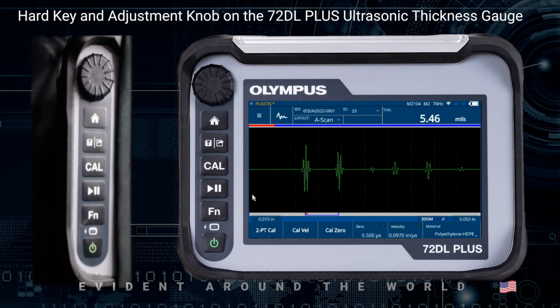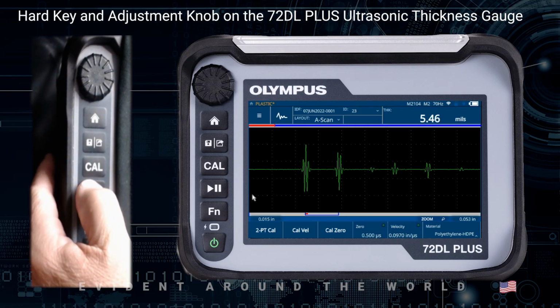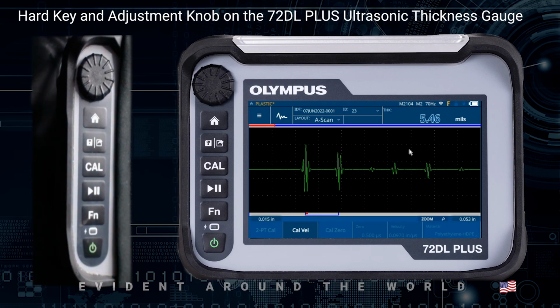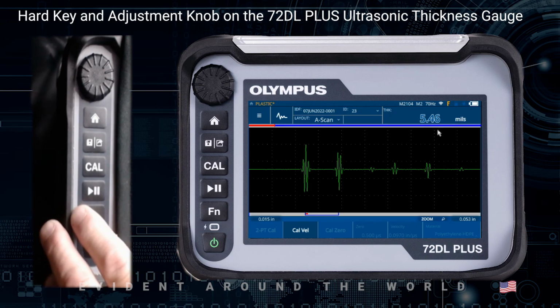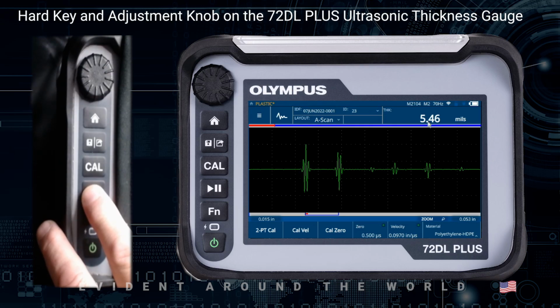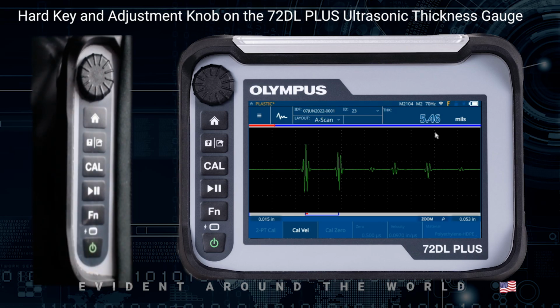Below the cal key is the pause and play key, or the freeze and unfreeze key, if you will. What this does is it simply pauses or freezes the display. So pressing it the first time will pause or freeze the display. You'll notice that a small F is displayed at the top of the display, and the thickness reading is displayed as an outline trace when it's frozen. When it's unfrozen, it goes back to a white solid number display, and as it's frozen, it goes into a reverse videoed outline trace number.